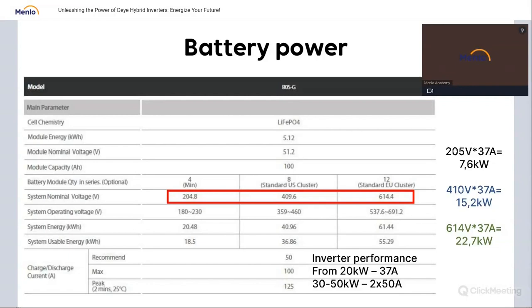volts times 37 amps. It means that with a system up to 20 kilowatts with the minimum set of batteries, you have 7.6 kilowatts of battery power. If you take more batteries, you have a higher voltage times 37 amps, which raises the maximum power which you can charge and discharge from the batteries. In the case of 30 up to 50 kilowatts, the inverter has the ability to charge and discharge with a current of 50 amps times 600 volts. With this biggest system, it means that one battery set of 12 batteries allows you to charge and discharge with more than 30 kilowatts.